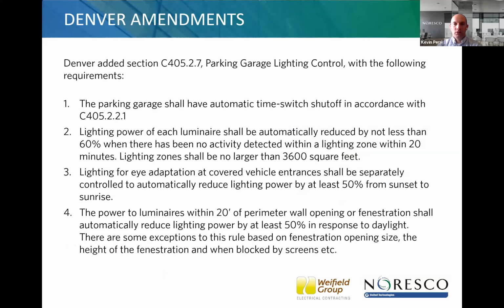So with that, I'll turn over to Jim Dent, who will cover the electrical amendments for Denver. Thanks, Kevin. Good afternoon, everybody. So Denver added section C405.2.7, parking garage lighting control. I saw one of the chats, people were wondering what's written into the 2021 code. The 2021 IECC does have parking garage lighting control in it. However, both Denver and Boulder, we'll see Boulder here in a few minutes, if you look at item number 2, lighting power of each luminaire shall be automatically reduced by not less than 60% when there's been no activity detected within the lighting zone for 20 minutes. Lighting zone shall be no larger than 3,600 square feet. That requirement is common to both Denver and Boulder in terms of 20 minutes, 3,600 square feet, and 60%. However, the 2021 IECC just requires a 30% reduction.